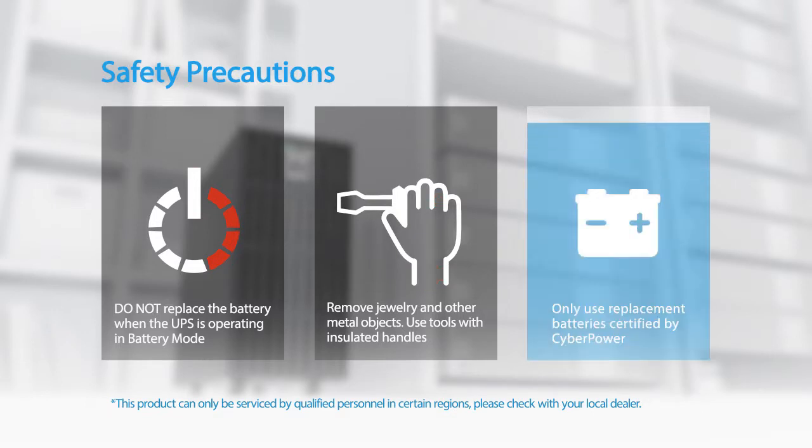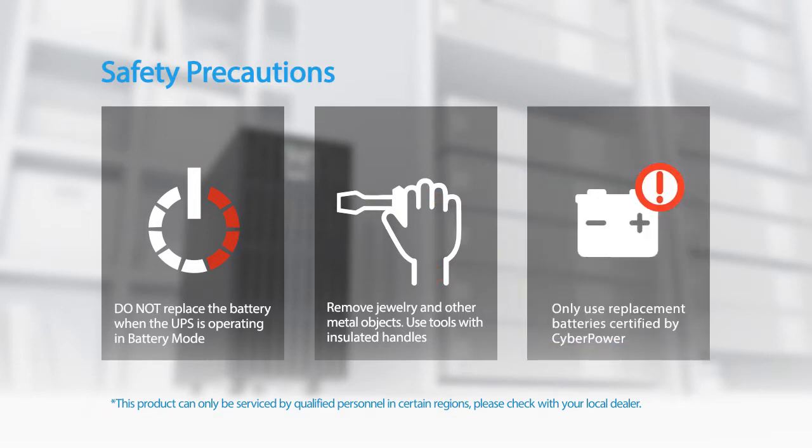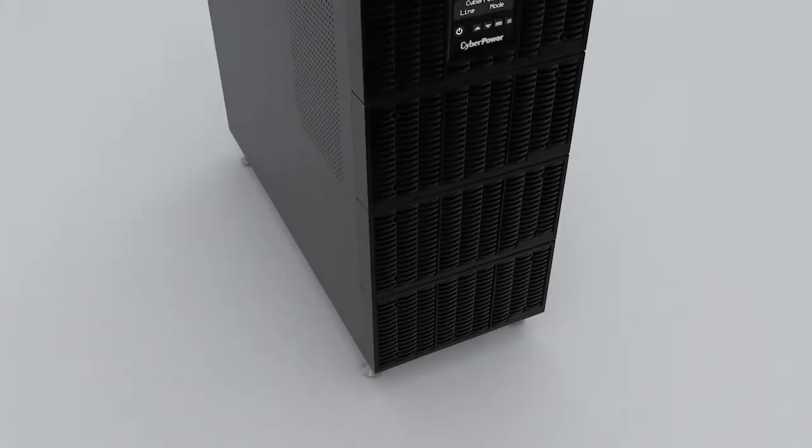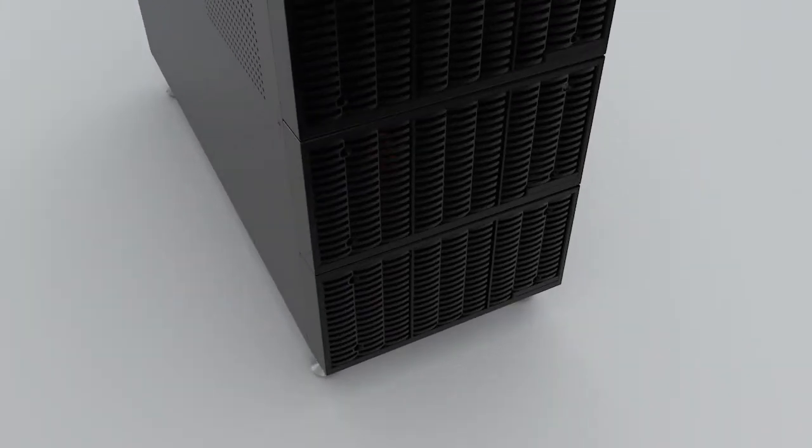Do not replace the battery when the UPS is operating in battery mode. Remove jewelry and other metal objects. Use tools with insulated handles only. Use replacement batteries certified by CyberPower. To start, remove the two lower front panels.